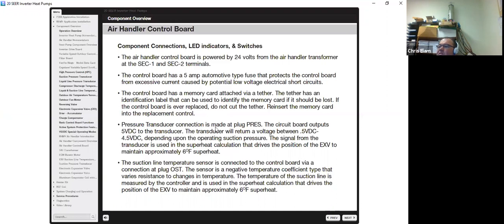You have your pressure transducer connection, which is made up of PRS. The circuit board outputs 5 volts DC to the transducer. The transducer will then return a voltage between 0.5 and 4.5 volts DC, depending on what the operating pressure is. So you can, in theory, look at your voltage and tell what your pressure is. The signal from the transducer is used to help calculate superheat and drive the position of the EXV to maintain exactly or approximately 6 degrees superheat.